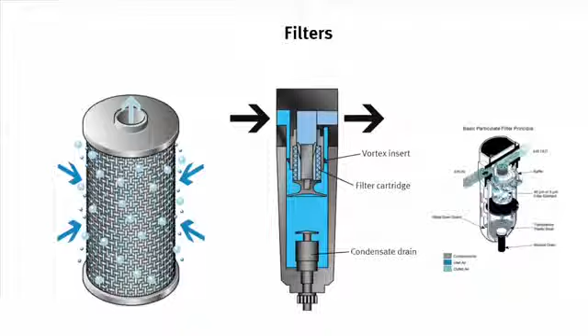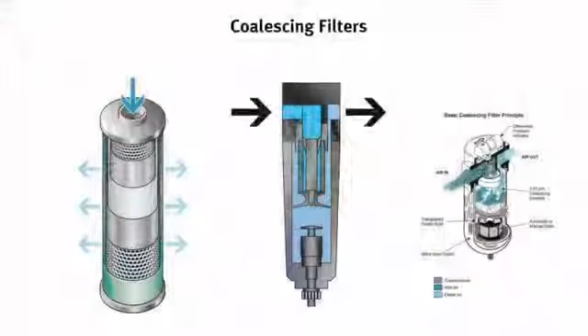To remove liquid water, we use water separators, which create a cyclone effect and spin the water to the outside of the chamber, causing it to collect in the bottom. To remove dust and water in the range of 40 to 5 microns, we use filters, which force the air through a sintered filter element, collecting the large particles in the bottom of the bowl. To remove smaller particles, as well as oil, in the range of 1 to 0.01 microns, we use coalescing filters.